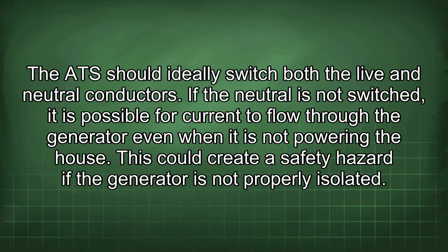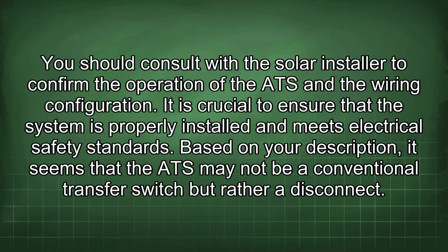The ATS should ideally switch both the live and neutral conductors. If the neutral is not switched, it is possible for current to flow through the generator even when it is not powering the house. This could create a safety hazard if the generator is not properly isolated. You should consult with the solar installer to confirm the operation of the ATS and the wiring configuration. It is crucial to ensure that the system is properly installed and meets electrical safety standards.